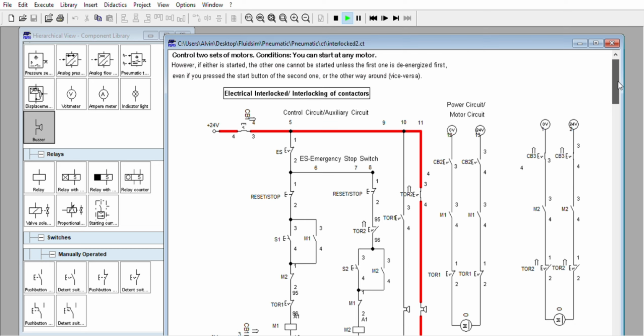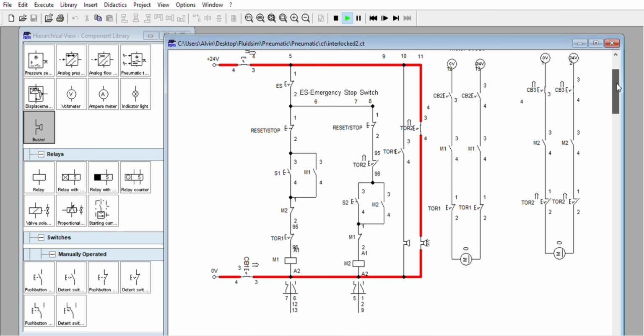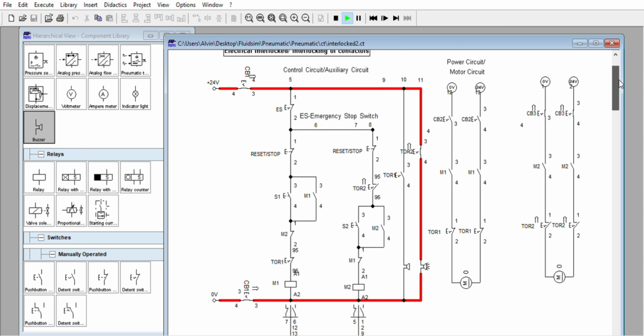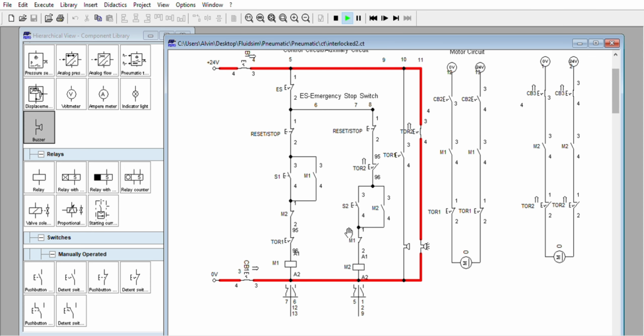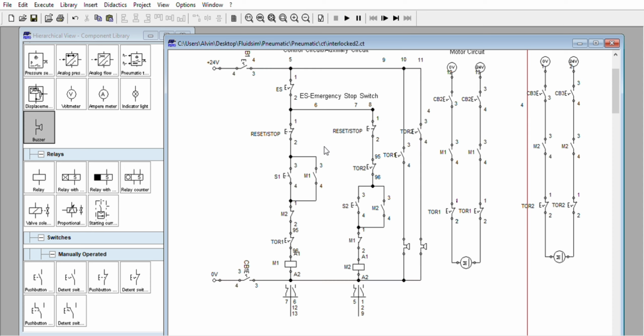So this is it, electrical interlock. In reality, we have mechanical interlock, wherein the mechanism of the magnetic contactors, they are installed together. They have mechanical interlock. So in that case, that is a mechanism. If this one is functioning first, a mechanical attachment will prevent the physical functioning of magnetic contactor 2. This one is functioning, there is a mechanical link, that is mechanical interlock. No electrical contact is involved.